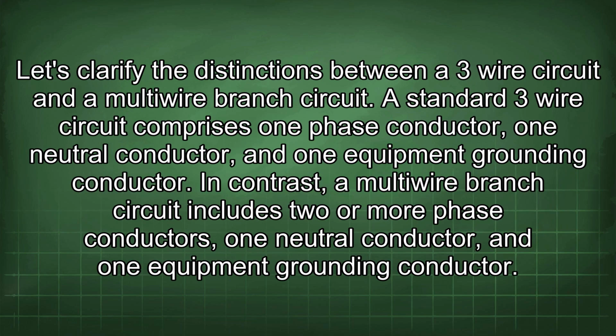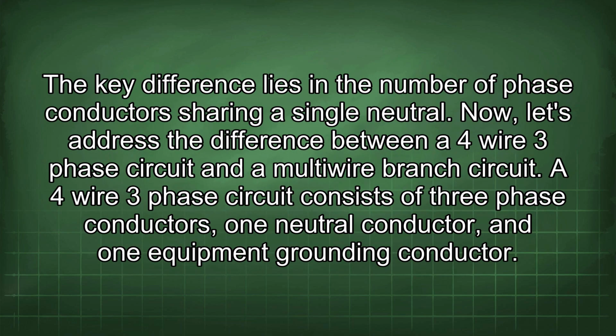Let's clarify the distinctions between a 3-wire circuit and a multi-wire branch circuit. A standard 3-wire circuit comprises one phase conductor, one neutral conductor, and one equipment grounding conductor. In contrast, a multi-wire branch circuit includes two or more phase conductors, one neutral conductor, and one equipment grounding conductor. The key difference lies in the number of phase conductors sharing a single neutral.